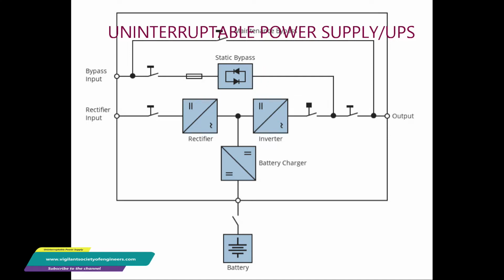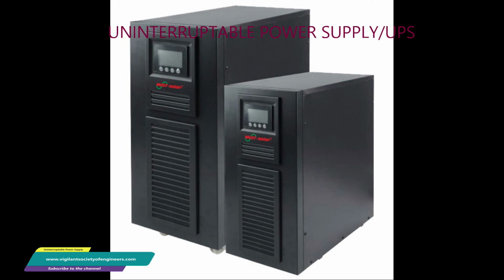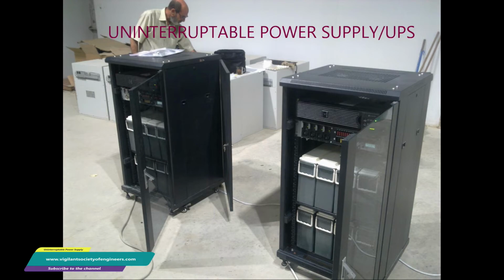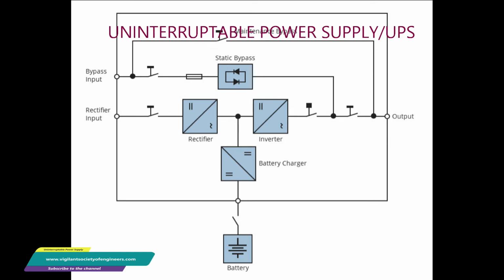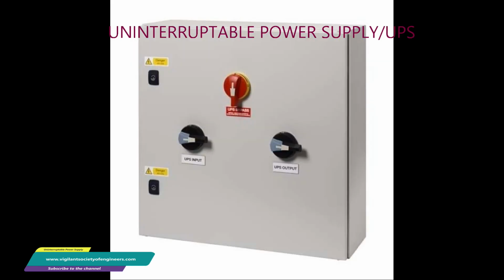So the next one we're going to look at is the UPS maintenance bypass. This is typically found in small UPS systems. The arrangement allows the load to be transferred under controlled conditions to the utility supply. The UPS can be shut down without loss of load, normally for routine UPS maintenance or repair. So in this condition, the switching is done internally within the UPS system during maintenance and testing, versus the external maintenance bypass. This is a feature built into the UPS system, so we use them wherever it's necessary or best suited.